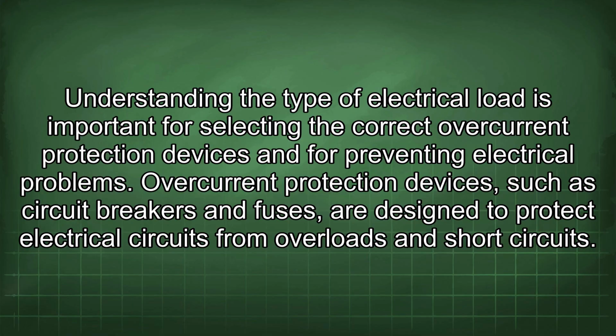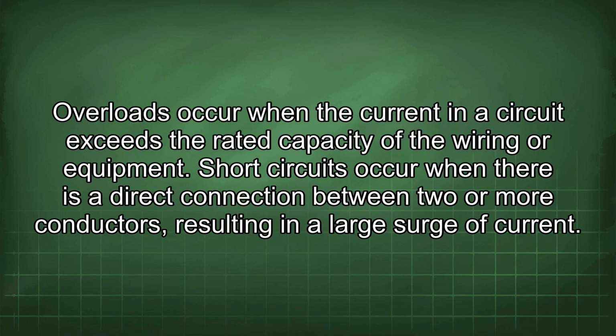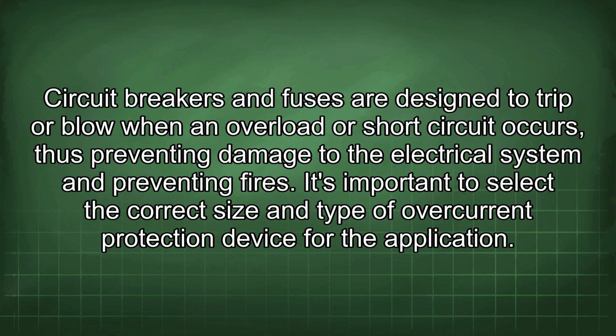Overcurrent protection devices, such as circuit breakers and fuses, are designed to protect electrical circuits from overloads and short circuits. Overloads occur when the current in a circuit exceeds the rated capacity of the wiring or equipment. Short circuits occur when there is a direct connection between 2 or more conductors, resulting in a large surge of current. Circuit breakers and fuses are designed to trip or blow when an overload or short circuit occurs, thus preventing damage to the electrical system and preventing fires.